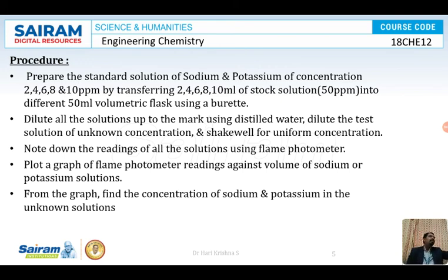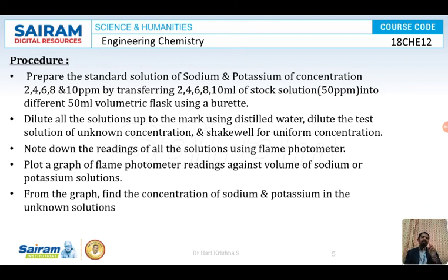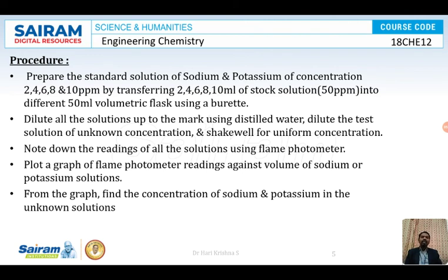Let us see how to prepare the standard solutions for sodium and potassium. We are going to prepare standard solutions of 2, 4, 6, and 8 PPM by transferring 2, 4, 6, 8, and 10 ml of a 50 PPM stock solution into different 50 ml volumetric flasks using a burette. These solutions are diluted to the mark using distilled water, and we also dilute the test solution. We label the flasks 2, 4, 6, 8, and note down the readings from all solutions using the flame photometer. We then plot a graph of concentration of sodium or potassium to determine the unknown solution.